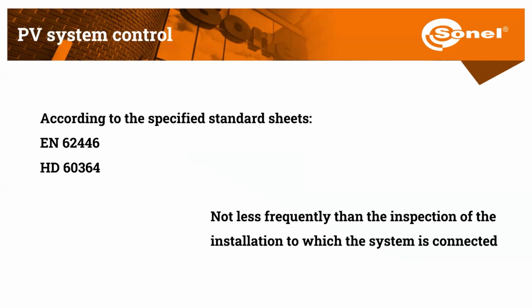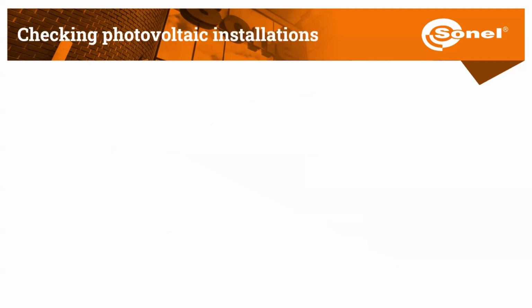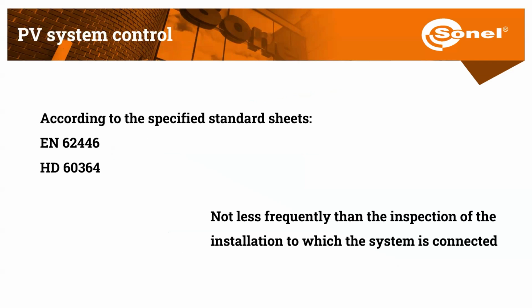In accordance with these two standards, it is assumed that the frequency of the periodic verification for the PV system should not exceed the frequency of periodic verification for the installation to which the PV system is connected. For example, in Poland, the periodic verification interval for a PV system connected to a residential or commercial installation is 5 years. However, if the PV system is connected to a specific risk place, such as a factory, this interval should be shorter. For example, a PV system connected to a petrol station must be checked every year.